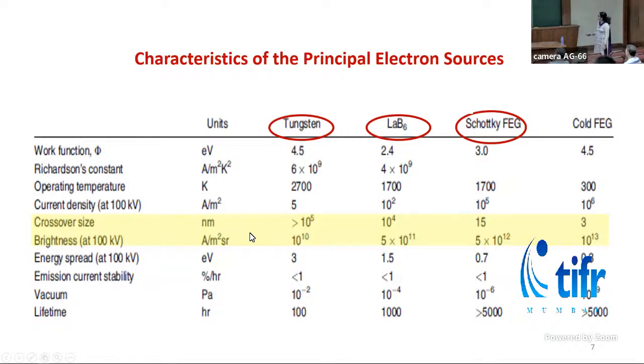Second thing to be noted is the brightness. The brightness decides the current in the beam. So here also we can see that tungsten has the brightness of the order of 10 to the power 10, and Schottky field emission gun has brightness of the order of 10 to the power 12. So this is very important when we are using the microscope as an analytical tool. So by looking at this, we can say that field emission gun gives the best resolution. Our EVO LS10 SEM has tungsten filament. Tecnai 200 kV TEM has a LaB6 filament, and HR SEM and Titan, they have this Schottky field emission gun.